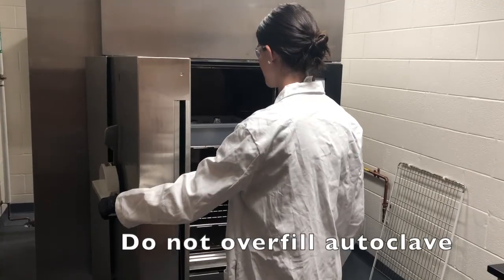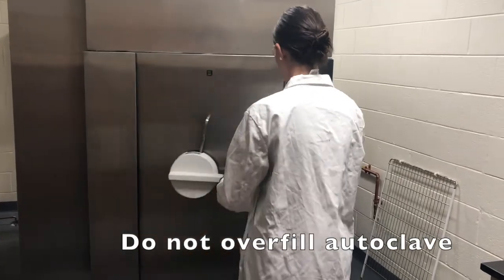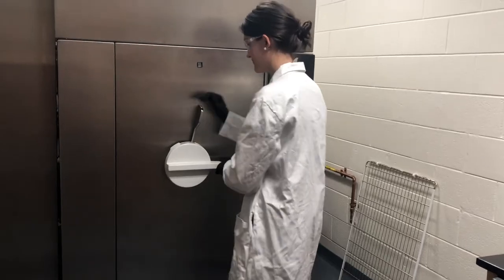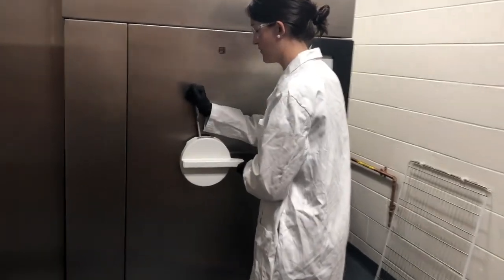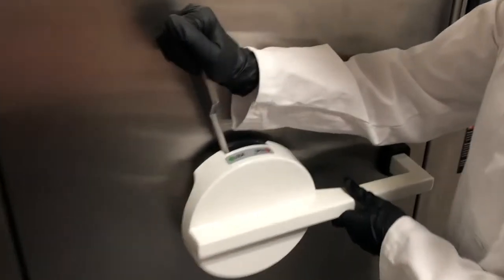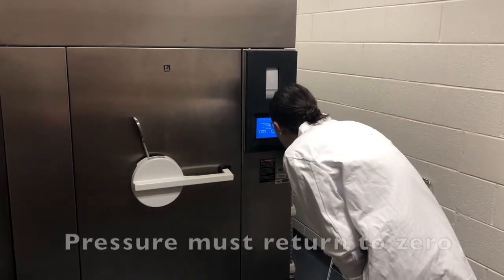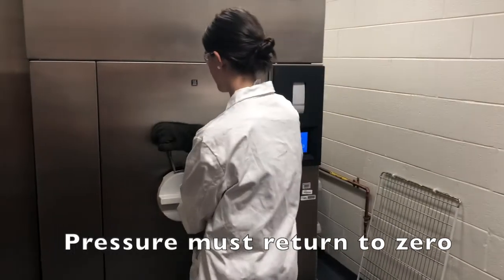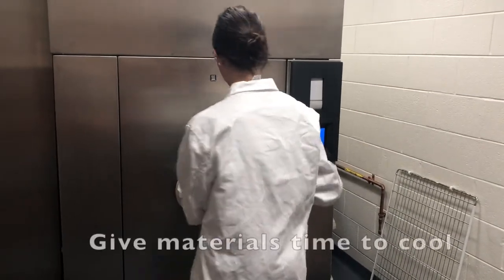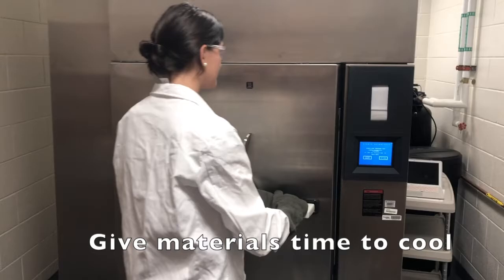When loading the materials, it is important not to overfill the autoclave. After the materials are loaded, carefully close the autoclave door and firmly lock it. The autoclave should run for 20 minutes at 120 degrees Celsius and the pressure should be between 15 and 20 psi. Once the cycle has finished, the pressure must return to zero before opening the autoclave door. The material should then be given time to cool before being handled.